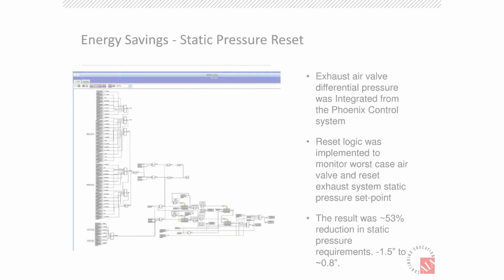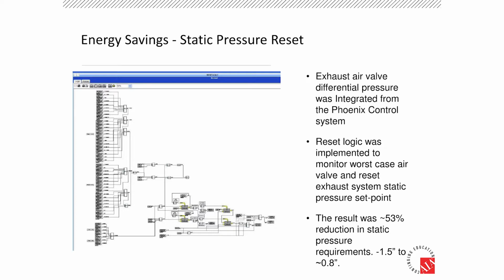So we were able to reduce the exhaust static pressure in the system from 1.5 inches to 0.8 inches. And when you're talking about, I think it was 12 or 15 dedicated laboratory exhaust fans that were all benefiting from this, we didn't take it to the step of calculating the energy savings yet, but we're getting there. So it's significant savings so far.